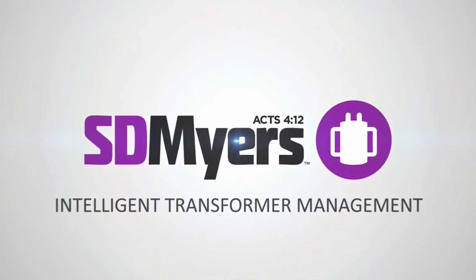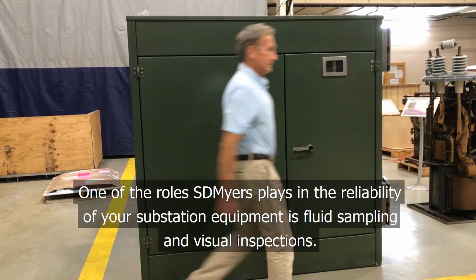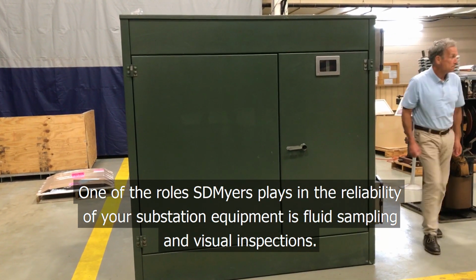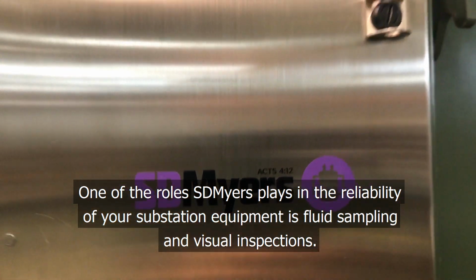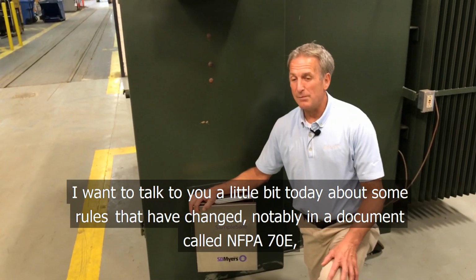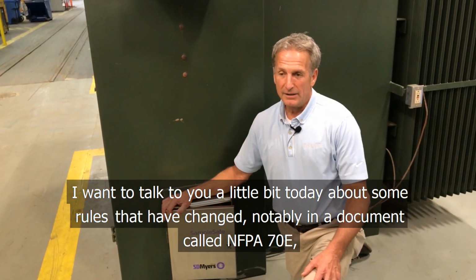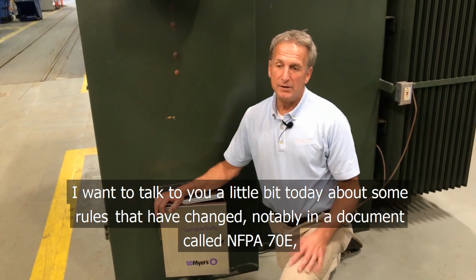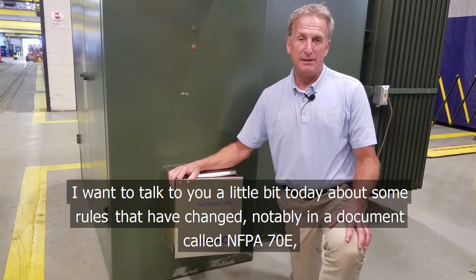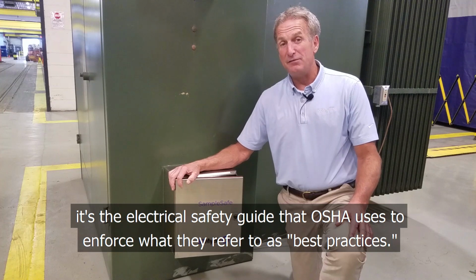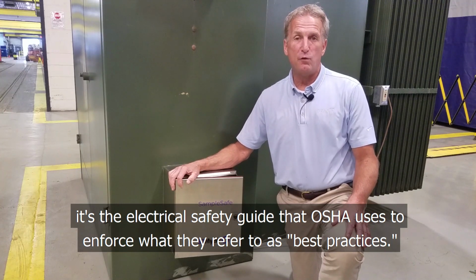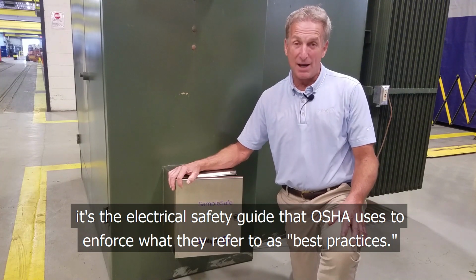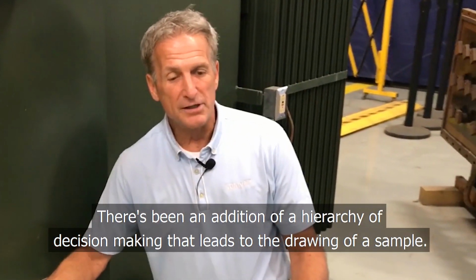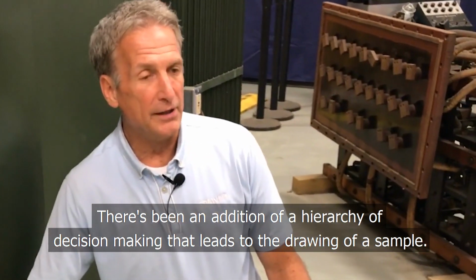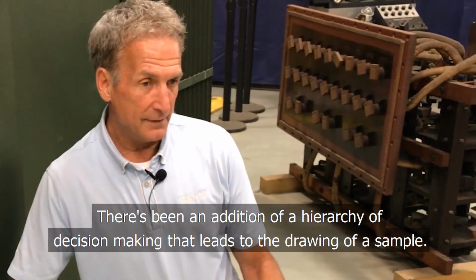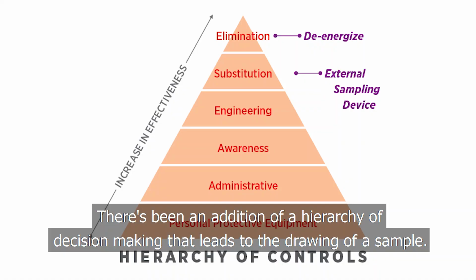One of the roles SD Myers plays in the reliability of your substation equipment is fluid sampling and visual inspections. And I want to talk a little bit today about some rules that have changed, and notably in a document called NFPA 70E. It's the electrical safety guide that OSHA uses to enforce what they refer to as best practices. There's been an addition of a hierarchy of decision making that leads to drawing of a sample.